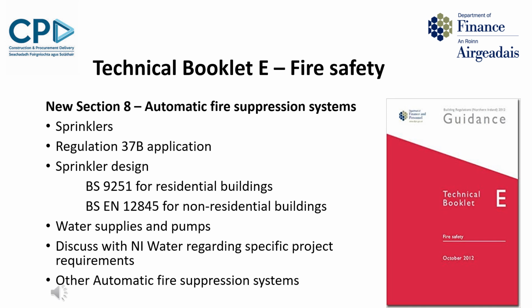Lastly, regarding other automatic fire suppression systems, evidence of performance testing and approval for use in buildings would be essential. The department's view is currently sprinklers are the only life safety systems capable of satisfying the requirements of Regulation 37B. If another system is chosen, then designers should demonstrate any such system gives an equivalent or better level of performance to that of an automatic sprinkler system.